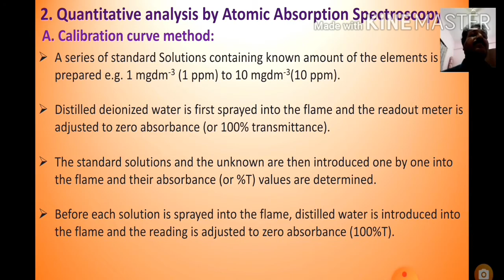Then distilled deionized water is first sprayed into the flame and the readout meter is adjusted to zero absorbance or 100% transmittance. The standard solutions and the unknown are then introduced one by one into the flame and their absorbance or percentage transmittance values are determined. Before each solution is sprayed into the flame, the distilled water is introduced into the flame and the reading is adjusted to zero absorbance or 100% transmittance.